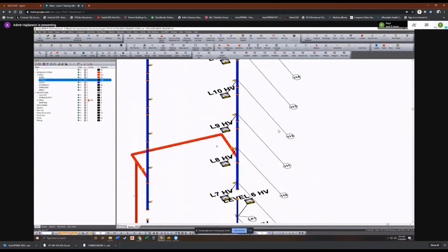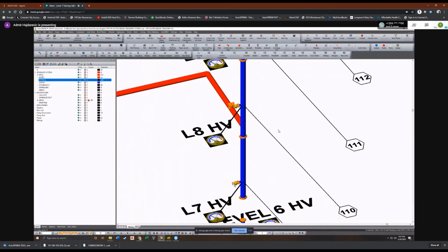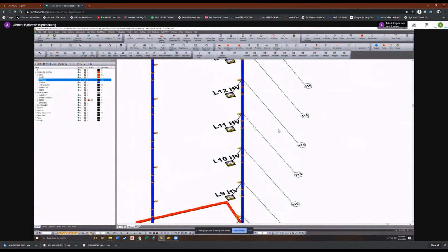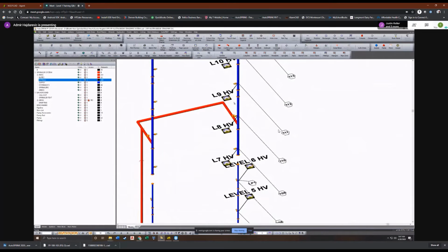But obviously, the drawback here is that instead of having that fixed flow of 500 GPM for this two vertical riser standpipe system, now you're going to have 500.1 or 500.2. So just be prepared that, having to take this approach, you might have a plan reviewer or somebody say, hey, how come you're not at exactly 500 GPM? What's this extra little flow for? And you might just need to explain, I had to flow a little bit extra to be able to populate pressure data below the interconnection point of these standpipes.